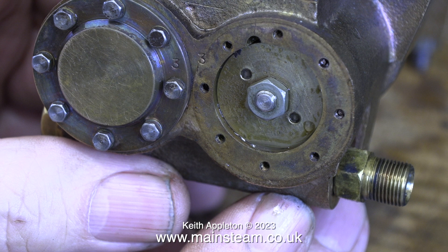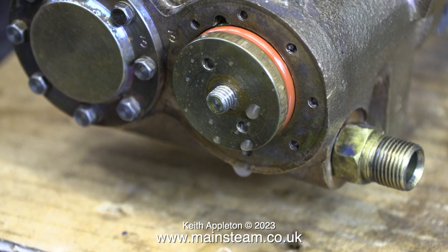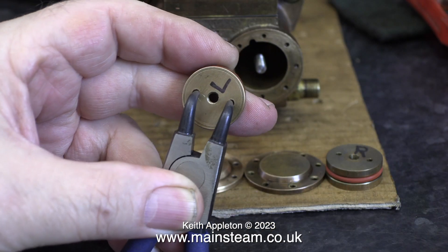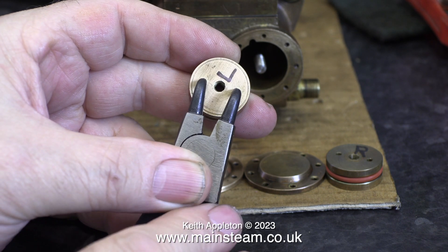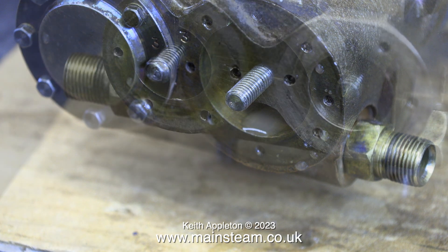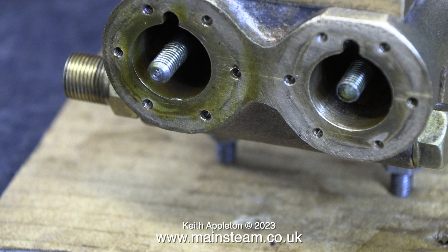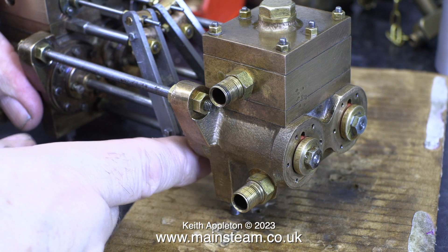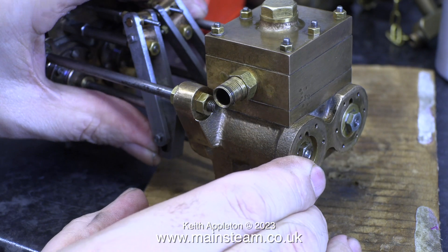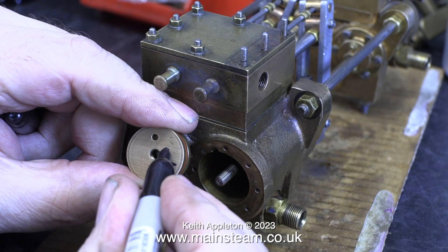This should be another top tip. When dismantling one of these pumps, start at the steam cylinder end, because there are two holes in each of the pistons. Not only can you hold the piston and piston rod solid using a pair of circlip pliers, while you undo the nut at the water cylinder end, followed by undoing the nut at the steam cylinder end, finally removing the steam cylinder piston using the circlip pliers. Before removing the steam cylinder pistons, I refitted the water cylinder pistons in place and fitted the lock nuts, only holding the piston rigid with the circlip pliers to tighten the lock nuts.